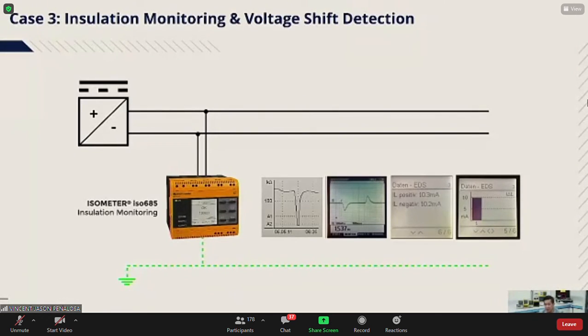Now, if you remember a while ago, depending on the leakage capacitance, the IEC actually tells you that an insulation monitoring device should be able to give you a measurement in 30 minutes. This thing can do it in 8 seconds, even in the highest leakage capacitance systems. It can do that.